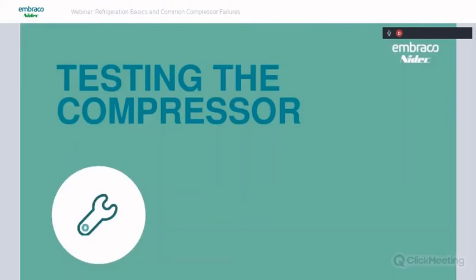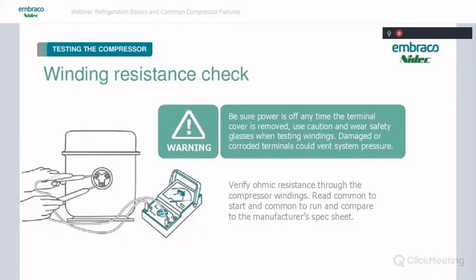So then moving on to testing the compressor. This is talking about testing the hermetic single-phase compressors. And there's two main checks you can do, and the first one is the winding resistance check. It's a very simple check you can do with your multimeter.